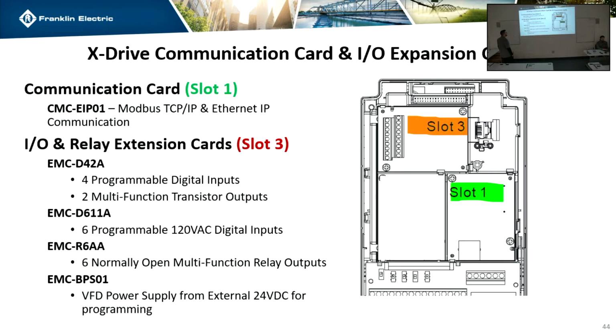So this is kind of going over what we did before, but just in a little bit more detail. The COM card, this is the part number for it to get you your TCP IP. These are the relay extension ones. So there's one that gives you extra inputs and outputs, which is multifunction outputs and 4 inputs. There's one that's all inputs, so it's your 120 volt digital inputs. I believe that drive right there has that card installed if we want to look at it. It's not turned on, but it's on the drive.